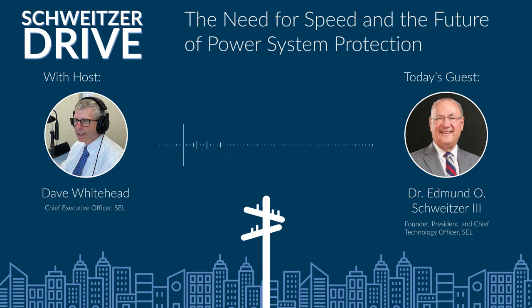So to do a good job, to be accurate, you really need a whole cycle, which would be, of course, almost 17 milliseconds at 60 hertz, 20 milliseconds at 50 hertz. So 16, 17 milliseconds is, I think, a really long time to leave a fault on a power system. And Kundur, in his book about power systems, said on high voltage and extra high voltage lines, the normal relay time is pretty much 1 to 2 cycles, and the circuit breaker times are 2 to 5 cycles.